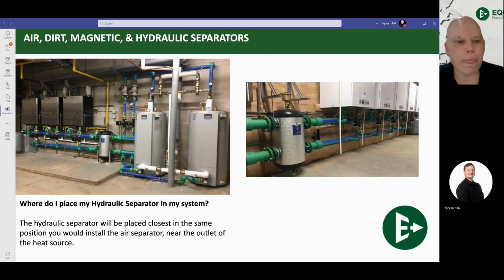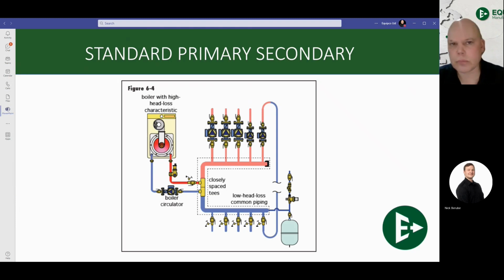Where we like to see them, again, is right after the boilers. It's from the boilers out and then from the system out. It's just those two little pieces. It separates the boiler side from the system side. That's really where they should be used with regards to the install. And you can put multiple boilers together and just get larger and larger hydraulic separators to do the exact same work. You just need to size them correctly and properly.